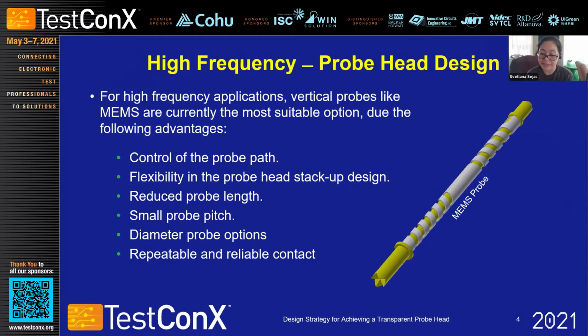We have flexibility in the stack up of the probe head, in the choice of materials and design techniques. We have short and long probes, so we can select which is the most useful in the design. And they are available for small pitch from 300 microns to 60 microns, and each of these probes is compatible with the others, and that is why we can mix probe diameters. In addition, we have a reliable and stable contact. All these are good characteristics to start the design of a high frequency probe head.